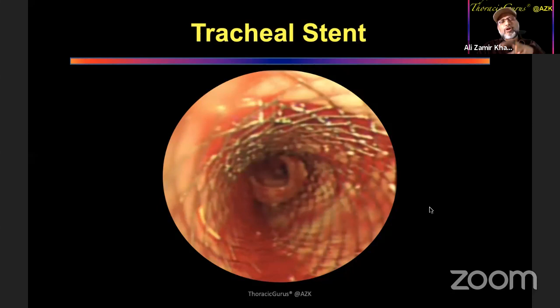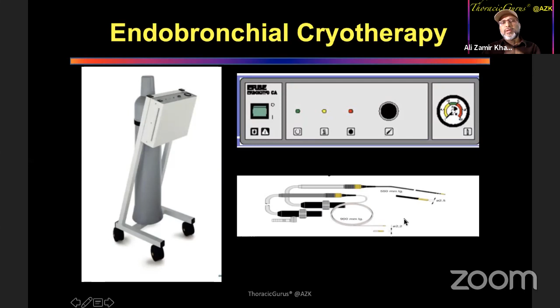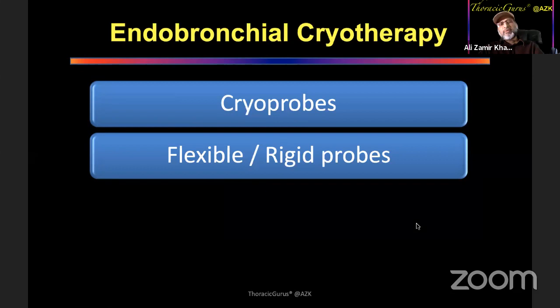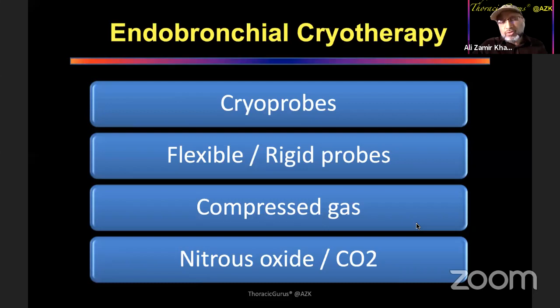This is how the probe looks. Here is your machine. Here is your cylinder of either nitrous oxide or CO2. And then this is a machine on which you connect. These are the various catheters that are available. You have flexible catheters and you have rigid catheters, okay? So cryoprobes can be flexible or rigid. You use compressed gas, which is usually nitrous oxide or CO2, okay?